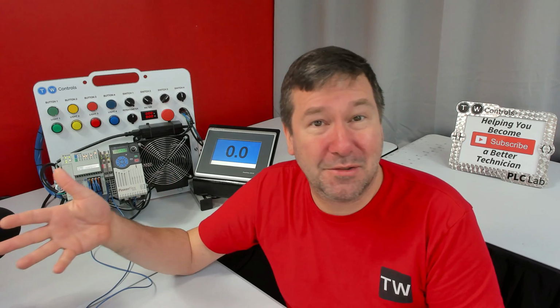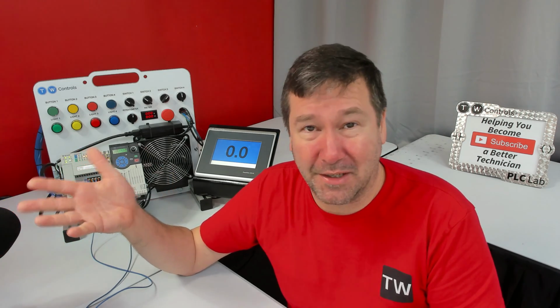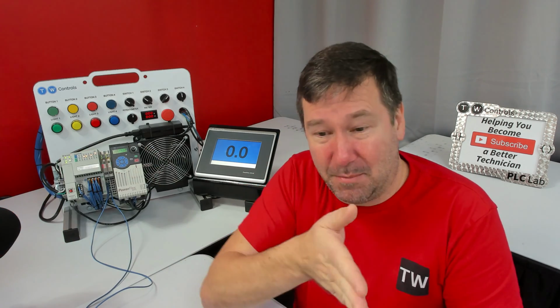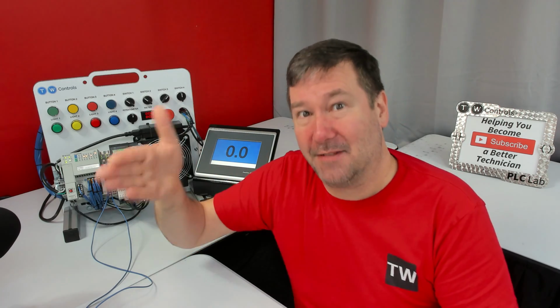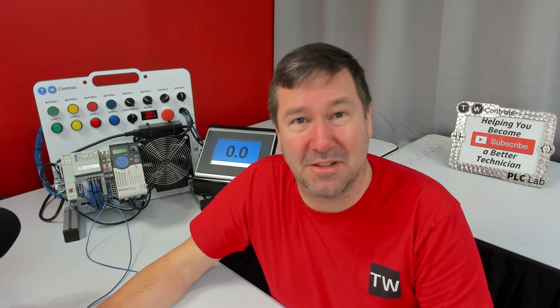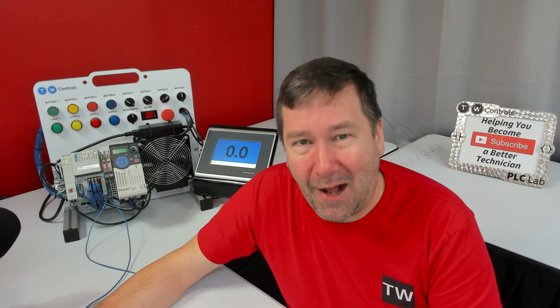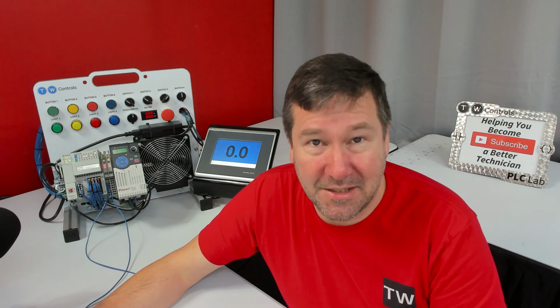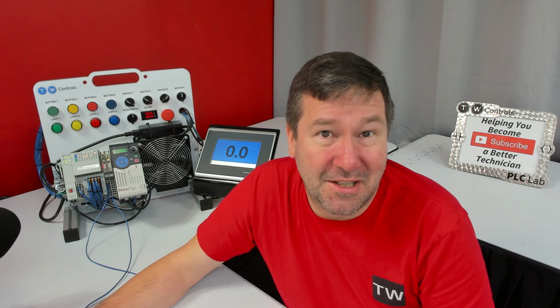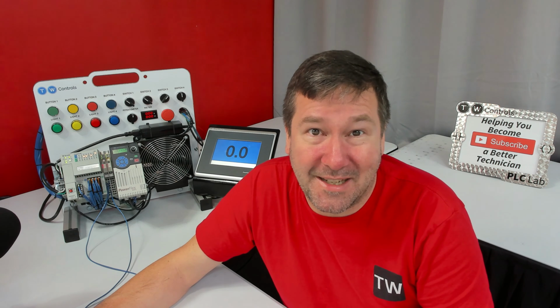Now, someone is going to tell me, hey, you could just change those engineering values to what you want. The issue is you lose precision. I'm going 4 to 20 milliamps. Well, it's an integer, so it's going to be 4, 5, 6, 7, 8, 9. I'm not going to have any resolution there. So overall, I disagree with changing these engineering units. Plus, when I'm troubleshooting, these are the numbers that most people expect to see.